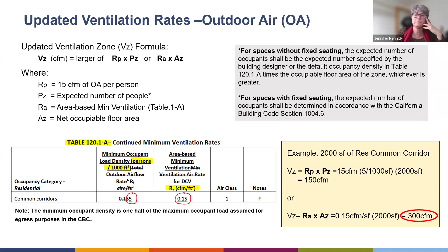And then on this table, we would also need to look at our area-based minimum ventilation, 0.15 CFM per square foot. That number hasn't changed in years, so that's a familiar number. But now we're going to take the larger of those two formulas based on those numbers. In this case, one formula gives us 150 CFM ventilation required, or 300 CFM. You pick the larger, 300 CFM, and then you move on. And so this table of values has all changed. If you're doing the performance computer method or working with your engineer, they'll figure that out for you. But I want to give you a heads up that that's changed.